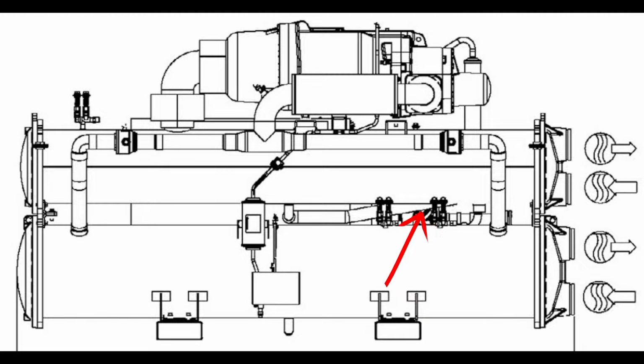We can see the EXV right here at this angle in the schematic. This is our metering device for this particular machine, right? You can just barely make it out there just behind these relief ports. So this right here is a double stack relief coming off of a service valve. Just behind these two reliefs, you can see the economizer. So there's the EXV for the braze plate and the economizer circuit. There's the EXV for the actual evaporator. So that feeds up to this insulated line, ejects into the bottom.